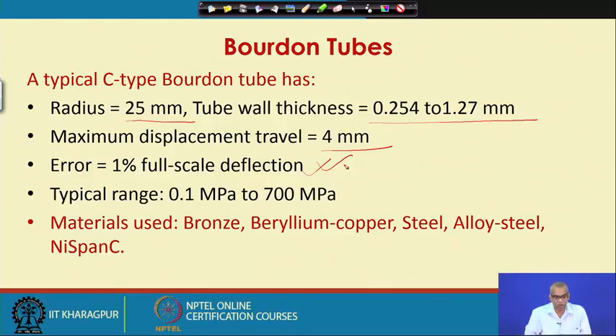The materials used for construction of Bourdon tubes are bronze, beryllium copper, steel, alloy steel, and Nickel Span C. Nickel Span C is an alloy whose modulus of elasticity does not change much with change in temperature. So, basically we can use materials for making a Bourdon tube which show good elastic property. Commonly used materials are bronze, beryllium copper, steel, alloy steel and Nickel Span C. Nickel Span C is an interesting alloy whose modulus of elasticity does not change with change in temperature.